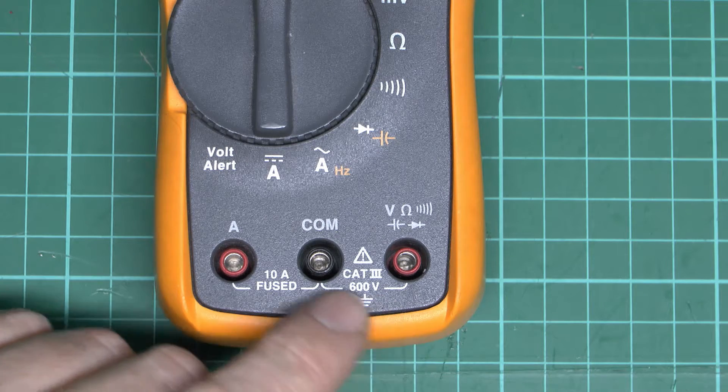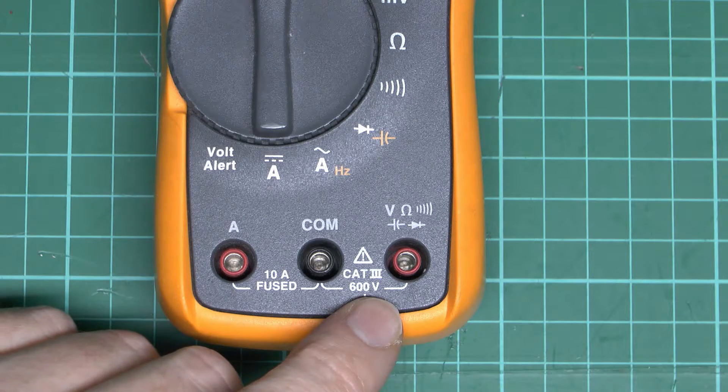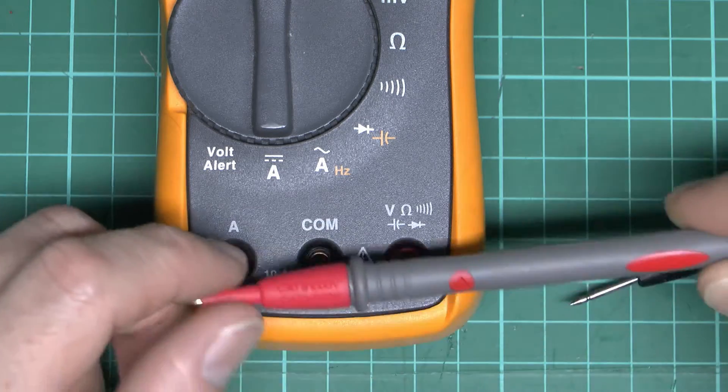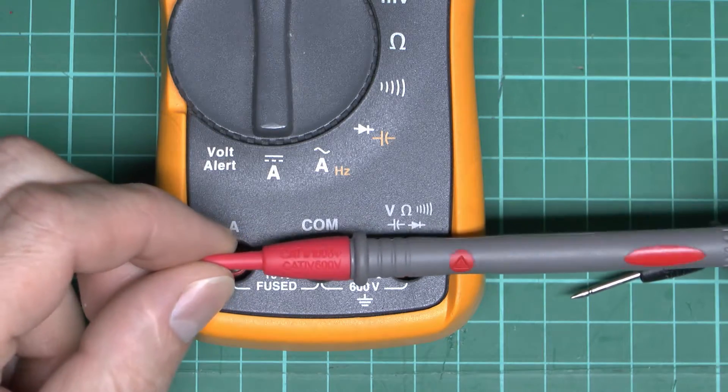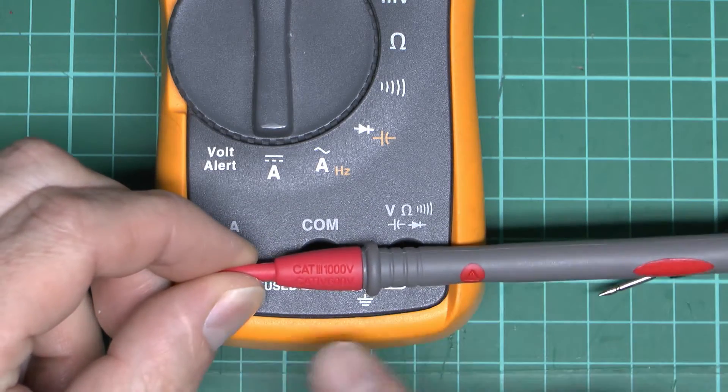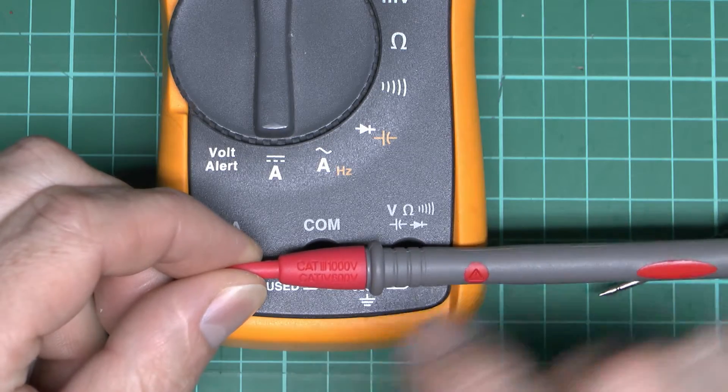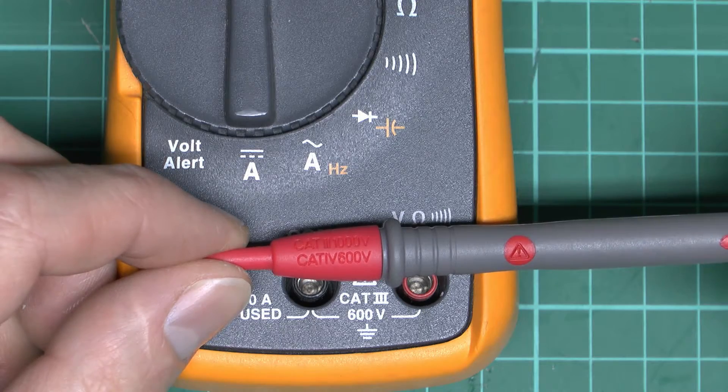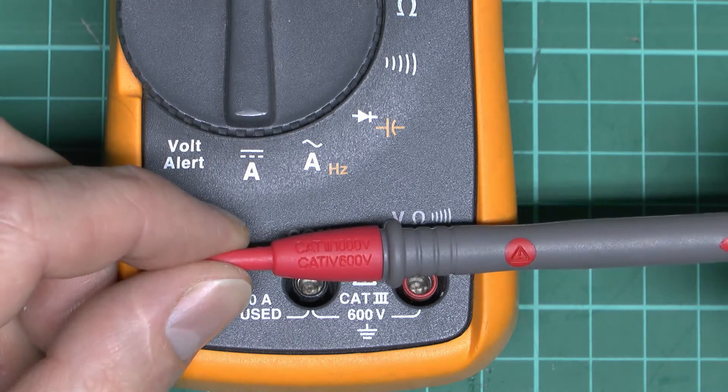And as well as the meter itself, or whatever measuring device you're using, it's also essential to make sure that the probes that you're plugging into this also have a similar rating on them. And here's an example of a probe here, and you see it's just printed on the end cap there. And you see this one is rated category 3 at 1,000V, and also category 4 at 600V.